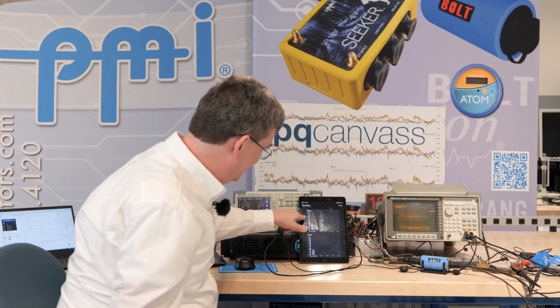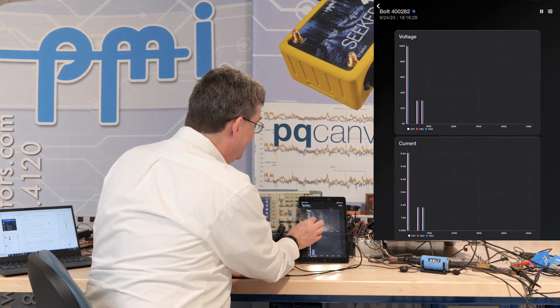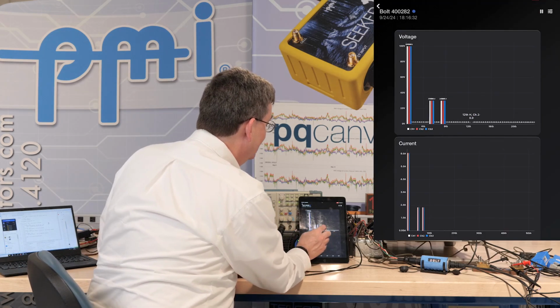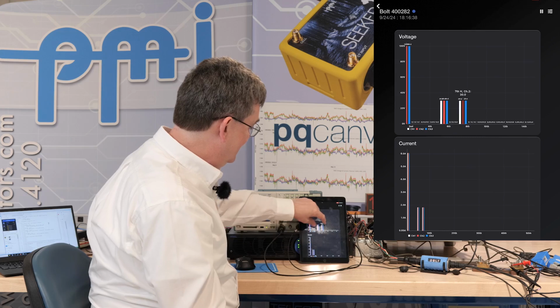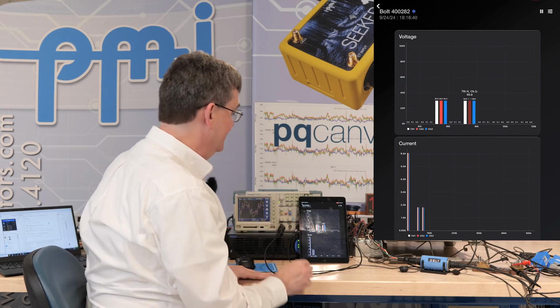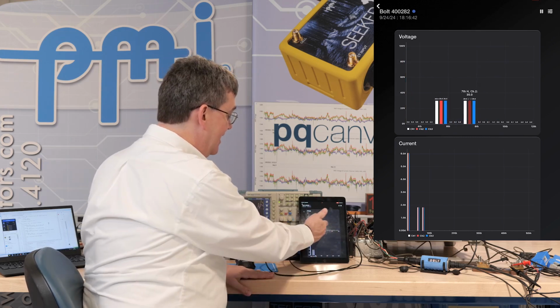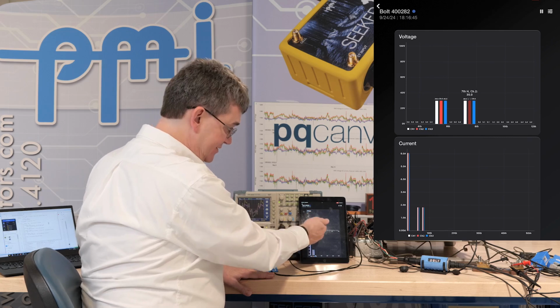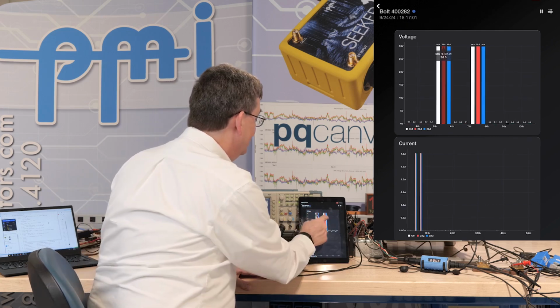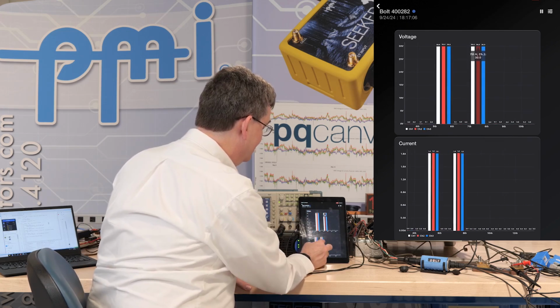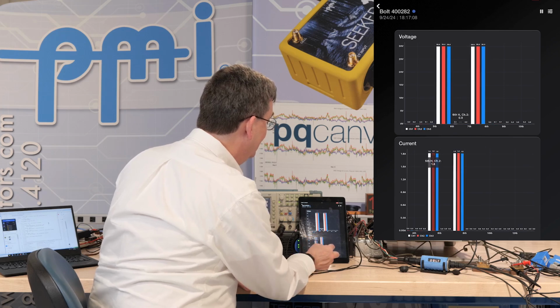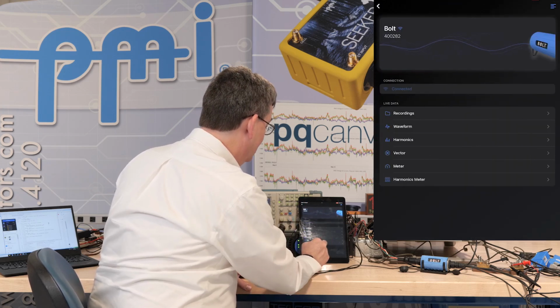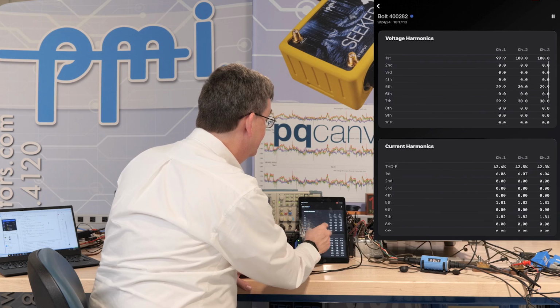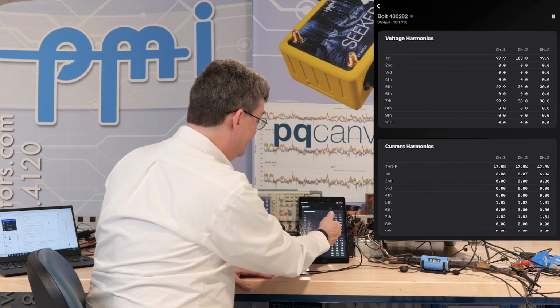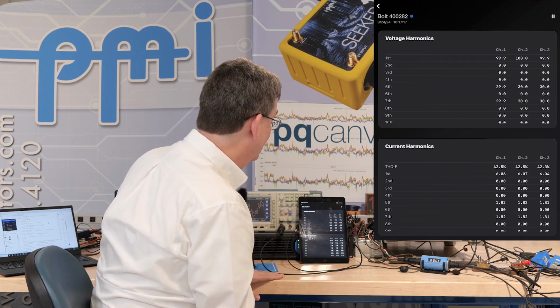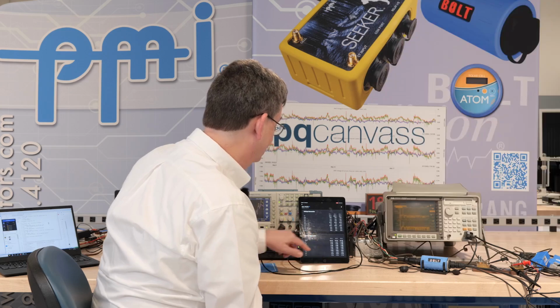We have, of course, 60 Hertz at 100 volts again, and we have 2 closely spaced harmonics here, the 5th and 7th harmonic. The test is to make sure that it's 0 in between, that there's no leakage from 2 high harmonics to one that's 0 in between. We can see these are 30 volts, with proportionally sized currents, and in between we have basically 0. Look at the meter reading to corroborate. 30, 29.9, and the 6th harmonic is exactly 0 for voltage and for current.